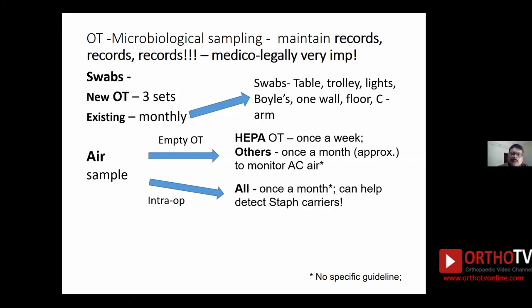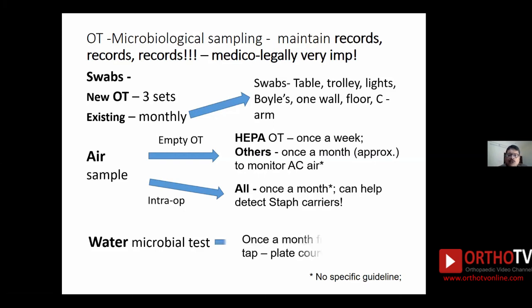Intraoperative air sampling is also recommended for HEPA filter laminar flow theaters, with once a month as the minimum recommended frequency. In my personal experience, intraoperative sampling helps pick up carriers of Staphylococcus aureus among OT staff — this is normally carried in the anterior nares and comes into the air with breathing, which can lead to surgical site infection in that theater. Water is also very important as it reaches every square inch of your OT through cleaning and disinfection processes and is used for surgical scrub. Once a month, water testing from the scrub basin tap should be done.